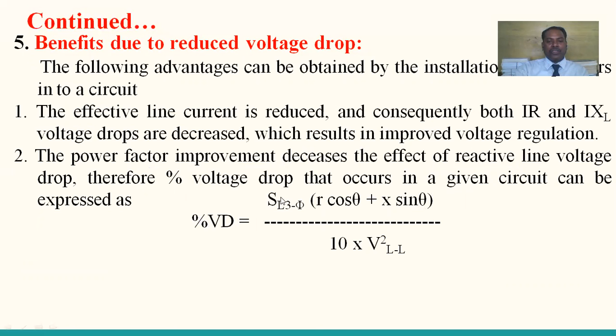And the second one, the power factor improvement decreases the effect of reactive line voltage drop. Therefore, the percentage voltage drop that occurs in a given circuit can be expressed as percentage of voltage drop is equal to SL 3 phase into R cos theta plus X sin theta by 10 into V line to line whole square. After application of capacitor, this voltage drop can be expressed as percentage of voltage drop is equal to QC 3 phase into X into L divided by 10 into V line to line square.